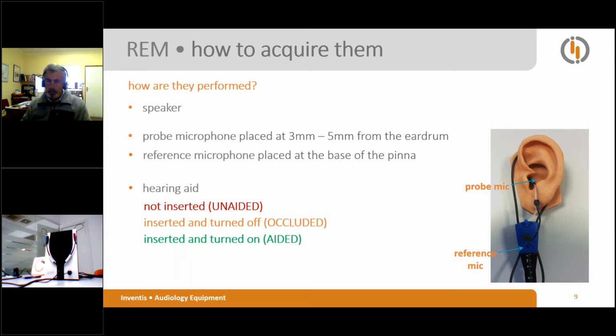Okay, so how are they performed? First of all, it is necessary to have a speaker. To perform an examination, a series of stimuli with a well-known spectrum and intensity are presented to the hearing impaired individual through a loudspeaker. Furthermore, the generated sound pressure is measured by means of two dedicated microphones. One microphone is closer to the eardrum, and it is the probe microphone. The other one is close to the pinna, and it is the reference microphone. They are both shown in the picture.